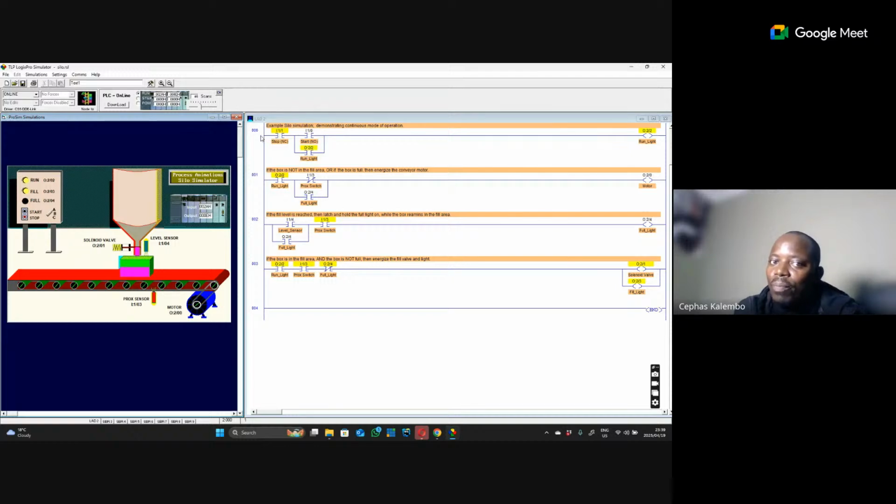So now we have got a path. Remember, a stop push button is normally closed, so here the signal is flowing. When it reaches here, the signal can't go through because this is open. It will come down here. But now this is latched because of the output. So we have got a continuous path like that. As you could see by that yellow light indication, this is allowing signal to pass, and that's allowing signal to pass continuously. This is only going to change if something changes on the input. And what's going to cut that flow is the stop push button.